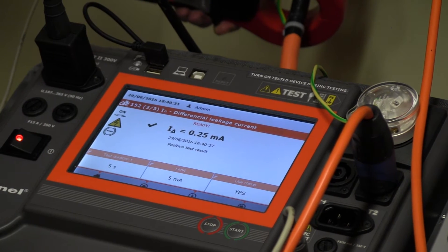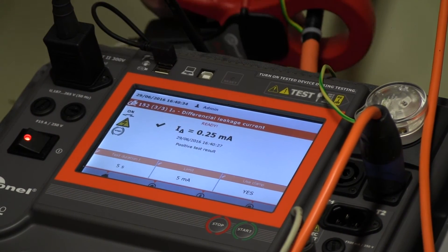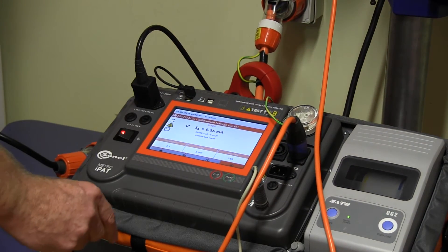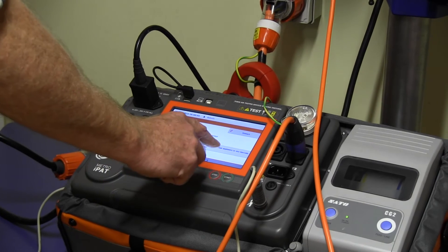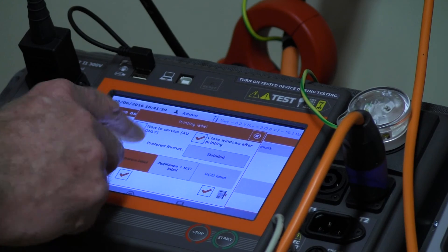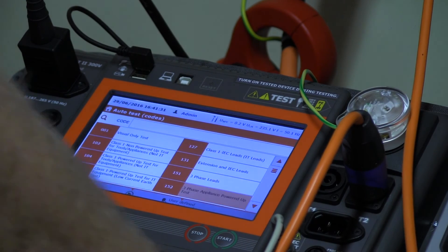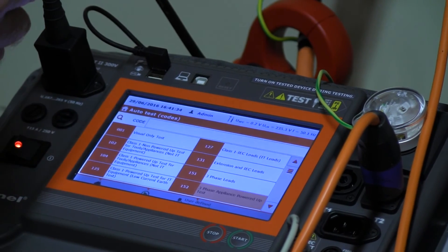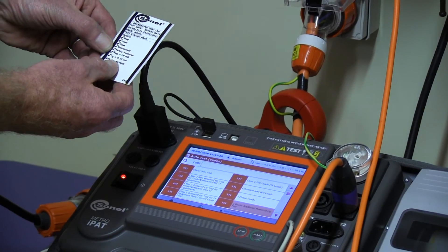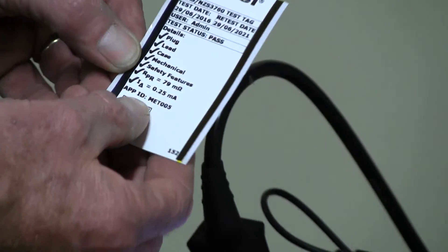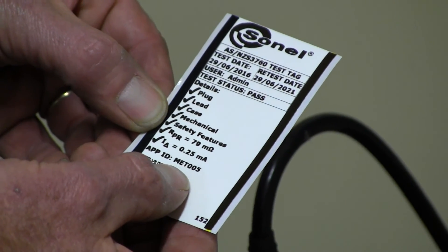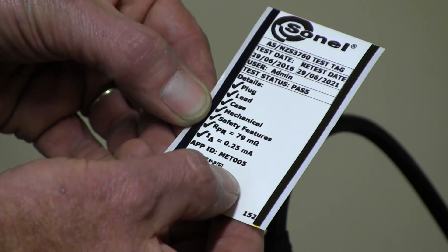It's finished taking the reading. We can print a tag from here. The three-phase tag says that all the safety features were good, the earth resistance was 79 milliohms, and the leakage was 0.25 of a milliamp. That's a complete test for a three-phase appliance.